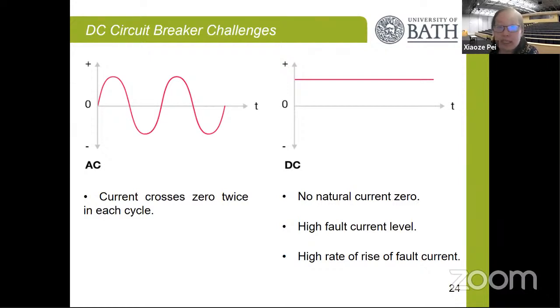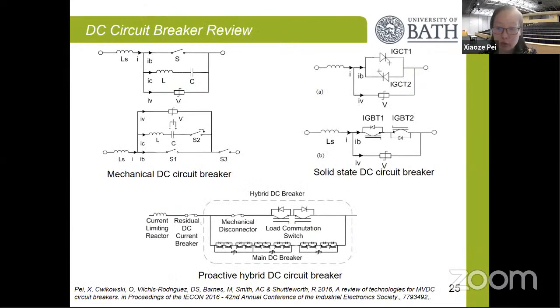So how do we deal with this? We carried out a review in this area to look at the current technology, for example, the mechanical DC circuit breaker. The mechanical DC circuit breaker has to have an auxiliary circuit, for example, an inductor and capacitor resonant circuit, to create an artificial zero crossing so that the mechanical switch is able to extinguish the arc. And the benefit of a mechanical switch is that it is a very mature technology, and it is also a very low loss operation.